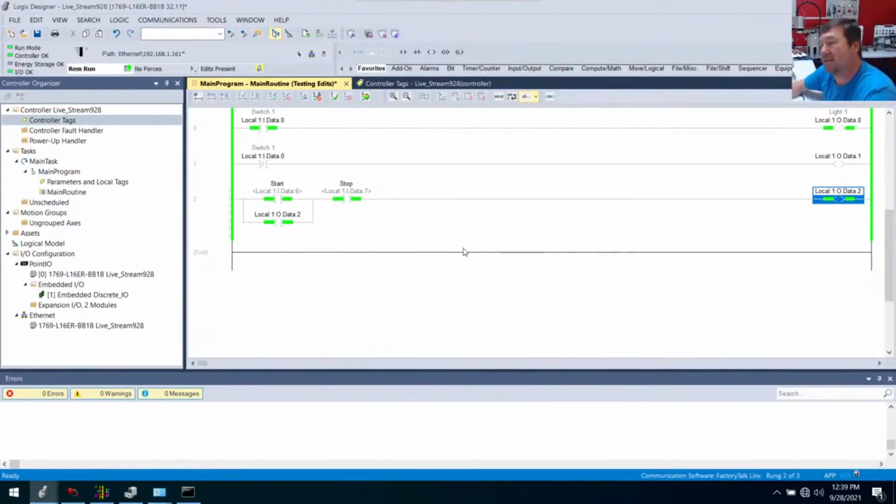Too many times I see programs that look exactly like this. Do not leave your program like this. People do. They're like, well, I think that works. Let me come back later. Now you need to make a decision now. Does this work or do we want to back out? And really, if you're sure it's going to work, then we need to hit this assemble button. Now the assemble button means make all this stuff permanent, delete anything we're not using now, and voila, now we have no letters by it.